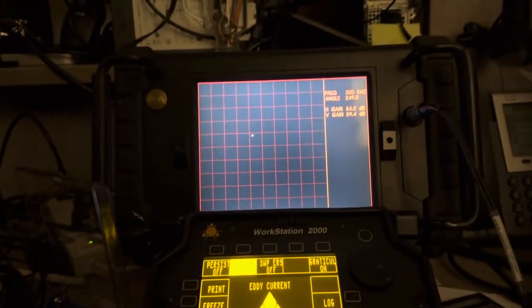And what I'm going to show you today, if I can get my camera angle right. What I'm working with here are titanium strips, and what you have is 5 strips on each side pushed together, so you have a 20 thousandths deep surface breaking notch or crack. And I've got them far enough apart, maybe a millimeter, so you get a nice signal. But for this particular probe and test frequency, that 20 mil deep crack is basically infinitely thick. So I could keep adding layers to that. With the crack in the middle, I'm not going to get a lot of difference in my results. So that's about as deep as you need to go for this experiment. Or I should call it a demonstration because I know the results already.